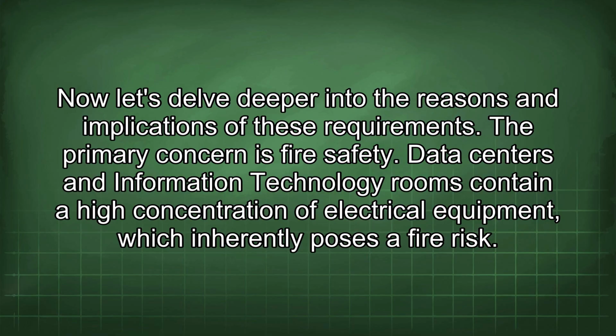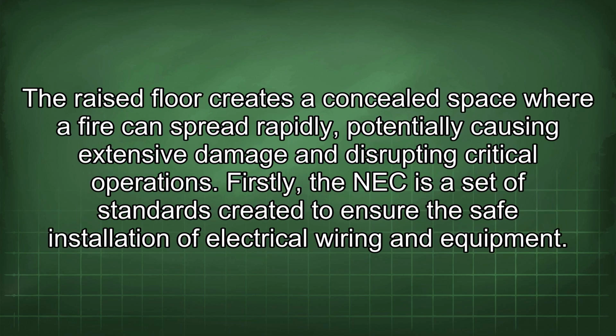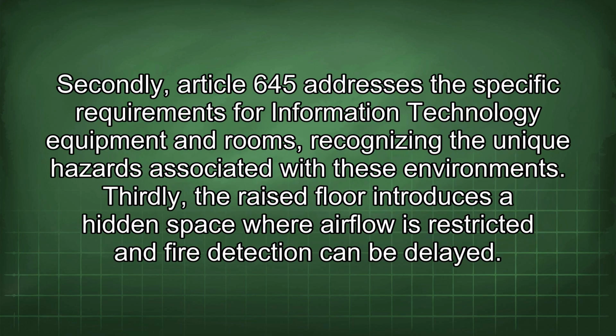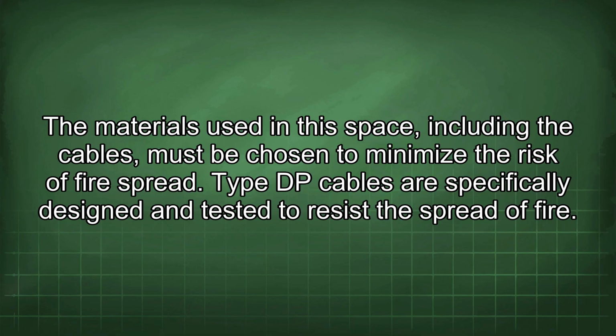The primary concern is fire safety. Data centers and information technology rooms contain a high concentration of electrical equipment, which inherently poses a fire risk. The raised floor creates a concealed space where a fire can spread rapidly, potentially causing extensive damage and disrupting critical operations. Firstly, the NEC is a set of standards created to ensure the safe installation of electrical wiring and equipment. Secondly, Article 645 addresses the specific requirements for information technology equipment and rooms, recognizing the unique hazards associated with these environments. Thirdly, the raised floor introduces a hidden space where airflow is restricted and fire detection can be delayed. The materials used in this space, including the cables, must be chosen to minimize the risk of fire spread.